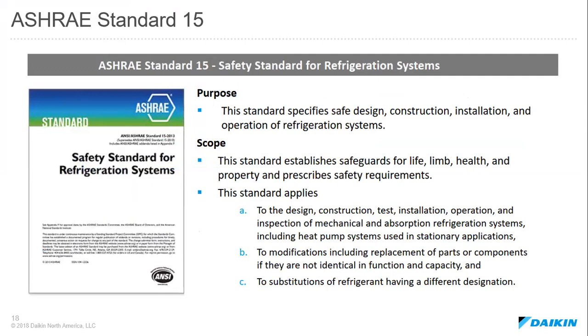ASHRAE Standard 15, as I mentioned earlier, is the safety standard for refrigeration systems. So this standard specifies how buildings can be safely designed, constructed, and equipment installed and operated. And the goal of this code is to establish a safeguard for life, limb, health, and property, and also give us some safety requirements. So this standard will typically be applied to the design, construction, testing, installation, operation, inspection of mechanical systems. And it will also be applied to modifications or replacement of parts and components if they're not identical in function and capacity. And then finally, it allows us to have substitutions for refrigerants that have a different designation.